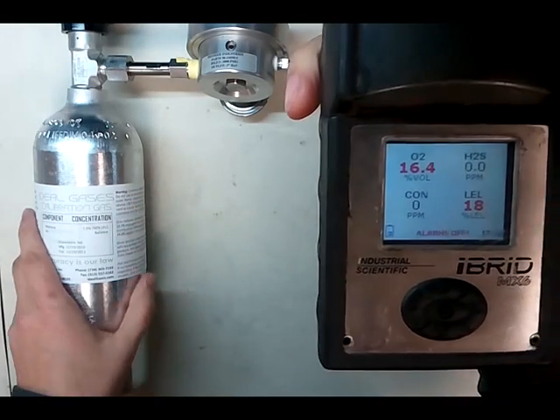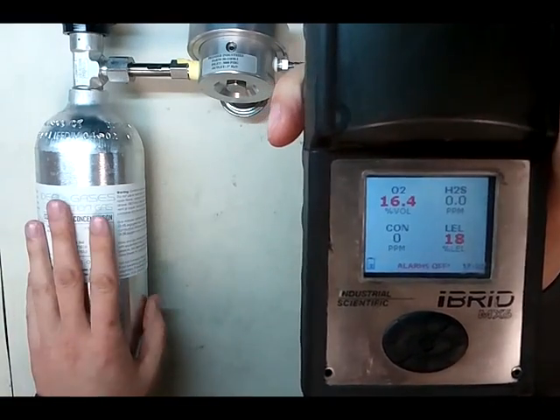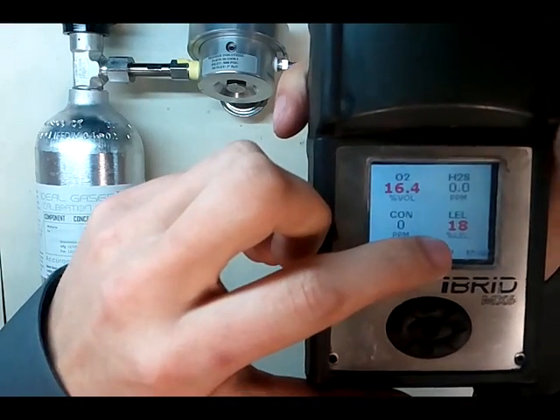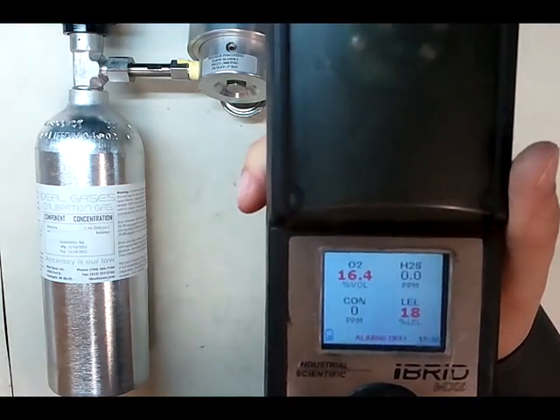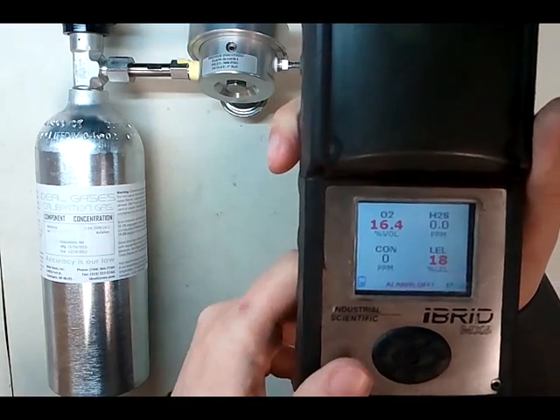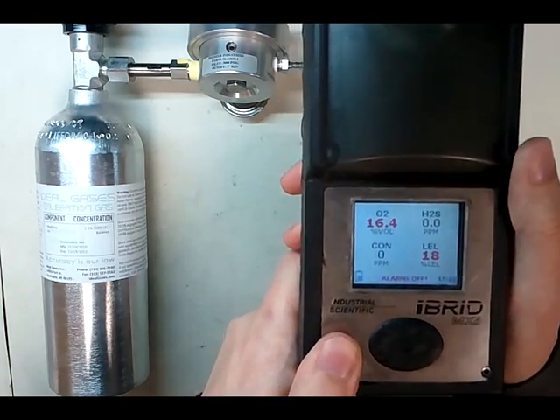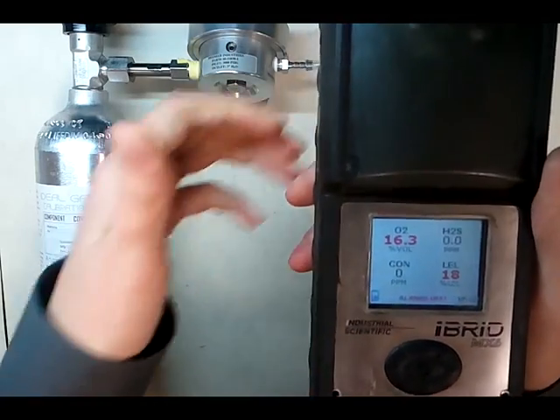That's a big deal. If you were in a field, it could be halfway to exploding and you're only seeing 18% on your meter. This is why I say not to calibrate using pentane ever.